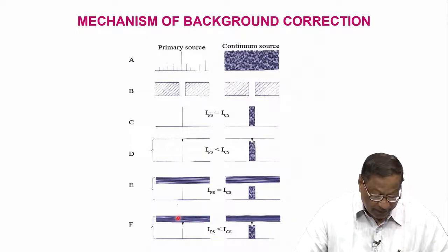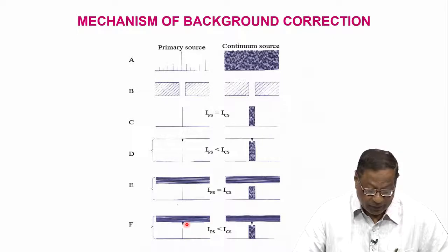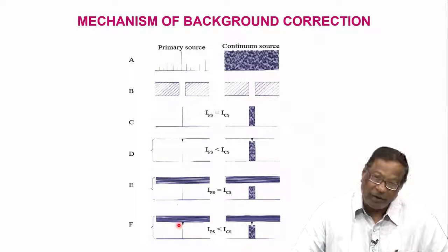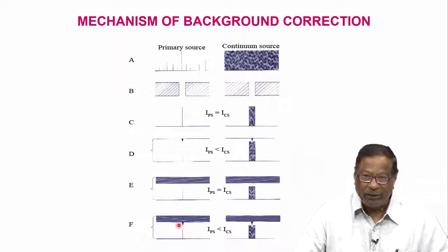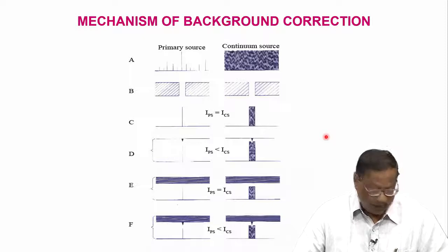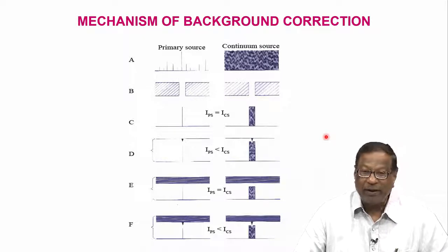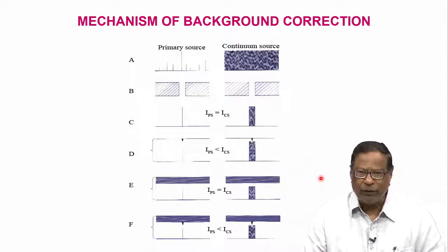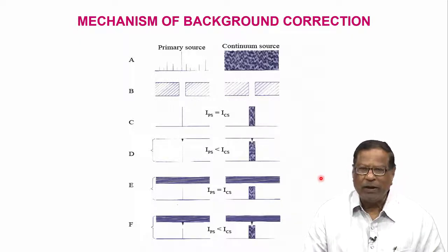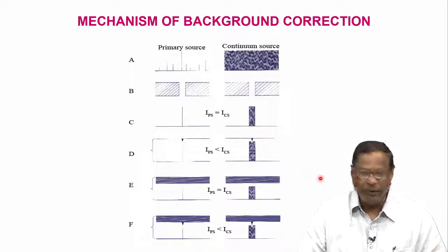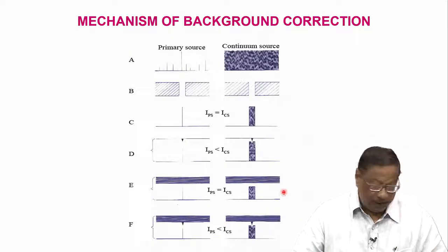That means it is the absorbance of the total background — not the atomic absorption — that we subtract. This is how the mechanism of background correction works. Along with the hollow cathode lamp, you switch on the deuterium lamp, and the electronics and other things will take care of the background.